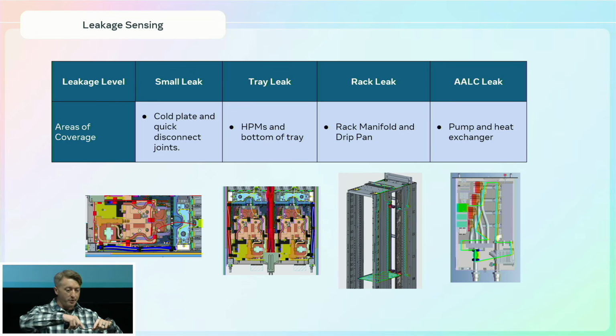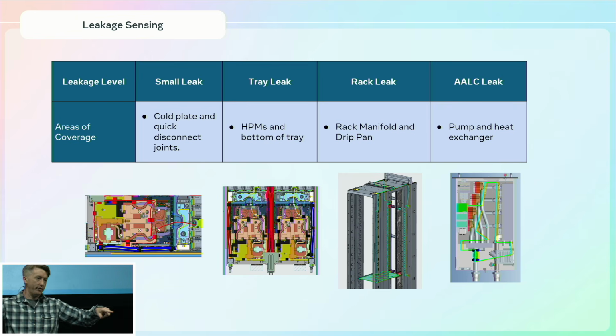These are wrapped around the HPM, the cold plate, where a majority of the liquid is flowing. Also within the bottom of the tray, it's snaked, so that if a leak makes it to the very bottom of the tray underneath everything, you can be pretty confident there's a notable leak occurring there, and you need to take action.